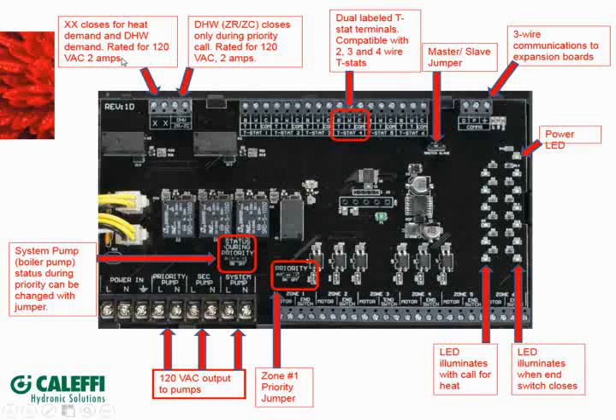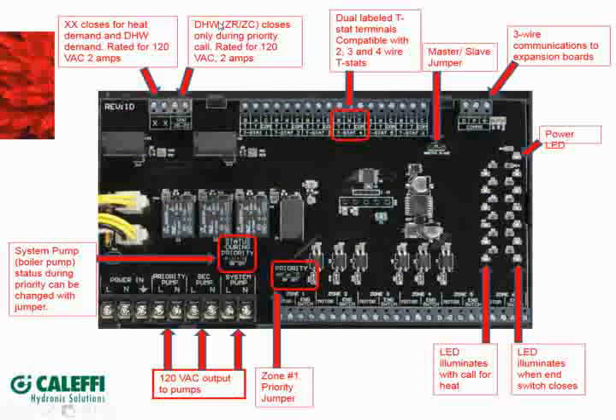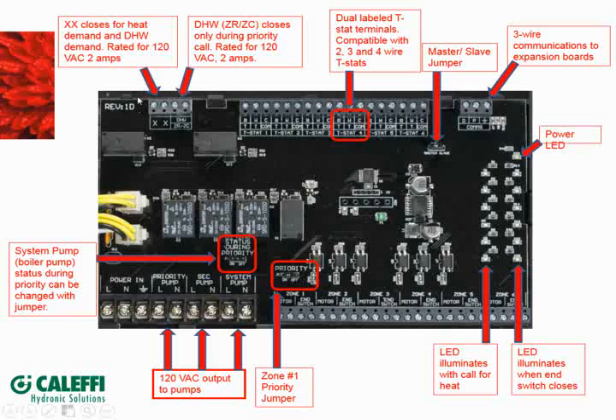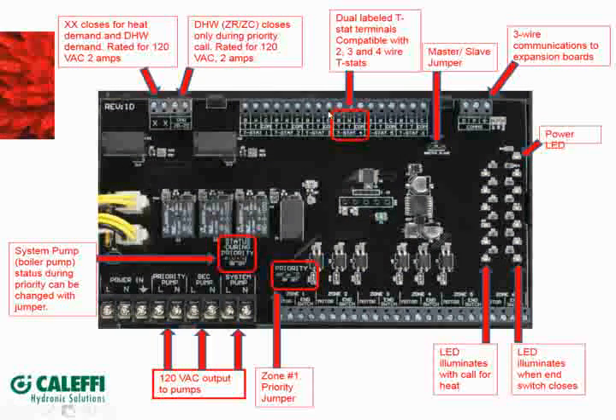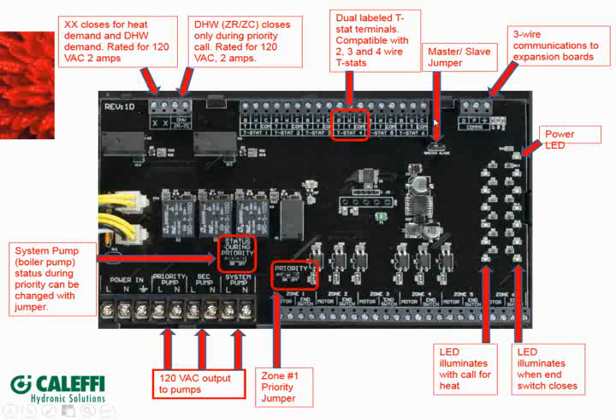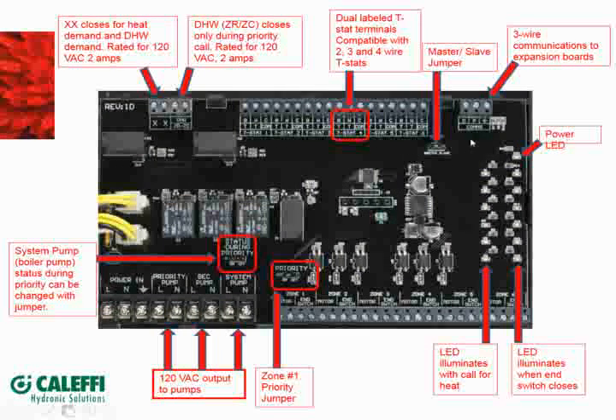So the XX, again, closes with a heat demand or domestic hot water demand, rated at 120 volts, 2 amps. Domestic hot water contacts, same deal, 120 volts, 2 amps. You can switch 24 volts here as well. Same labeling on our thermostat connections.